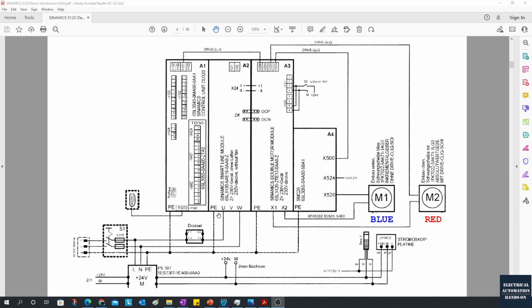We briefly review this diagram of this S120 servo drive system. We can see this is the CU, this is the in-feed module, and this is the motor module. And this motor module serves 2 servo motors here. The difference between these 2 motors: the encoder from this right motor goes directly to the motor module, via this DRIVE-CLiQ. DRIVE-CLiQ is a specialty protocol from Siemens. Physically it is like an Ethernet cable and Ethernet port. However, it is a special protocol from Siemens, used specifically for communication between the servo drive modules within the Siemens servo drive system.